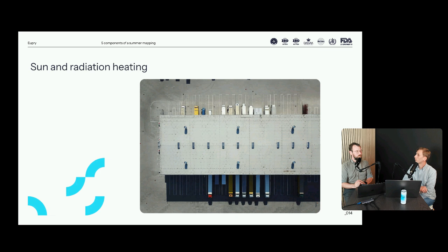Moving on to outside air temperatures - there aren't only downsides to summer mappings. We discussed earlier that by taking a risk-based approach, sometimes studies don't really make sense. One of the more amusing examples is if you have a 15 to 25 degree ambient storage area, and outside temperatures are somewhere in that range, say 20 degrees like today, you're not going to see anything, because it just aligns with the outside air temperature, which is within acceptable ranges.